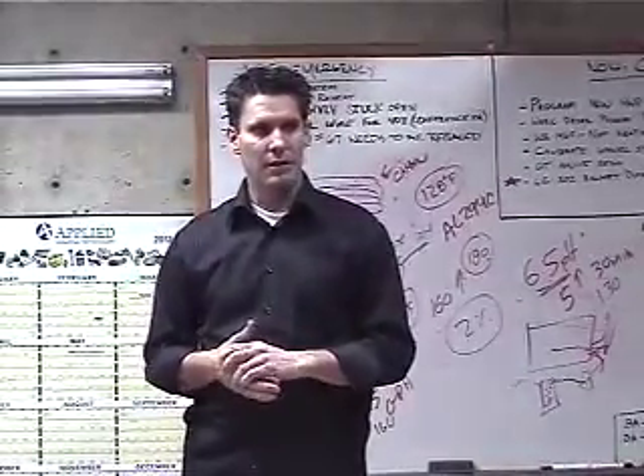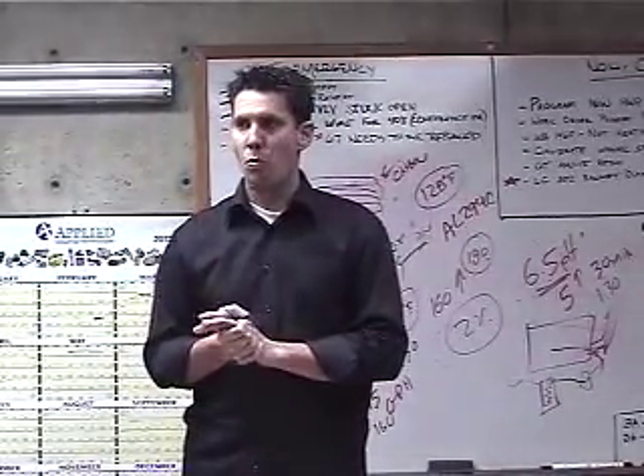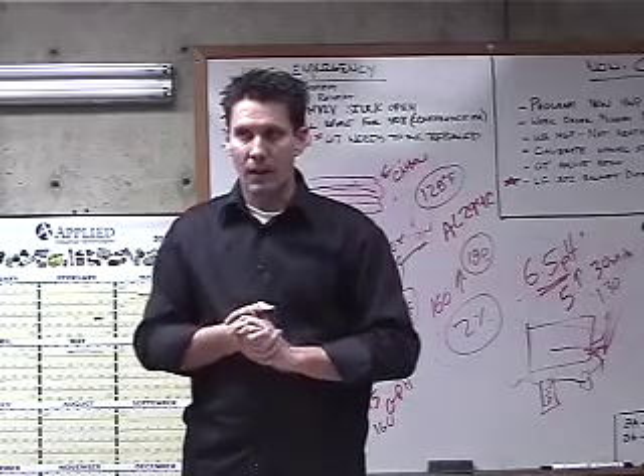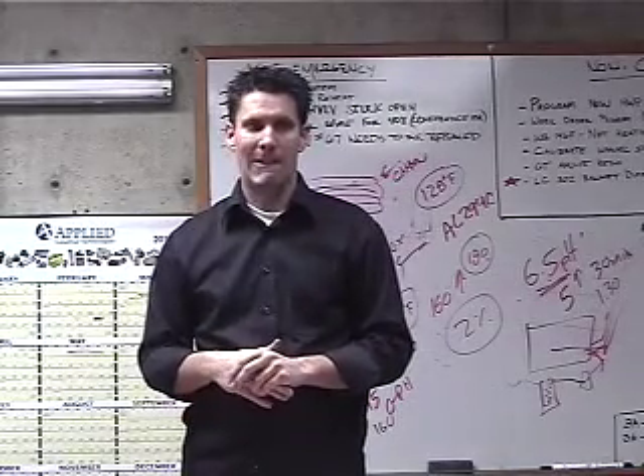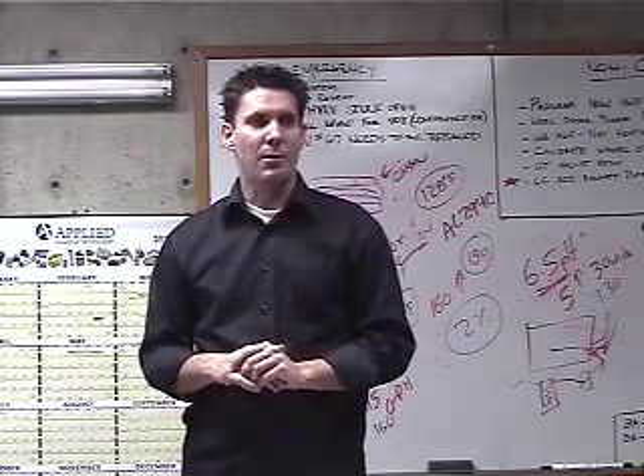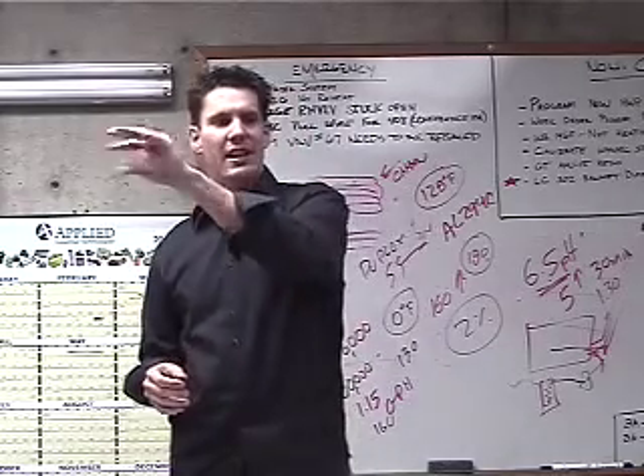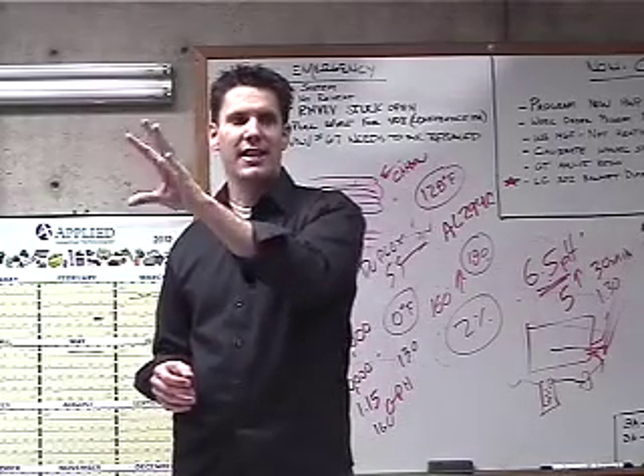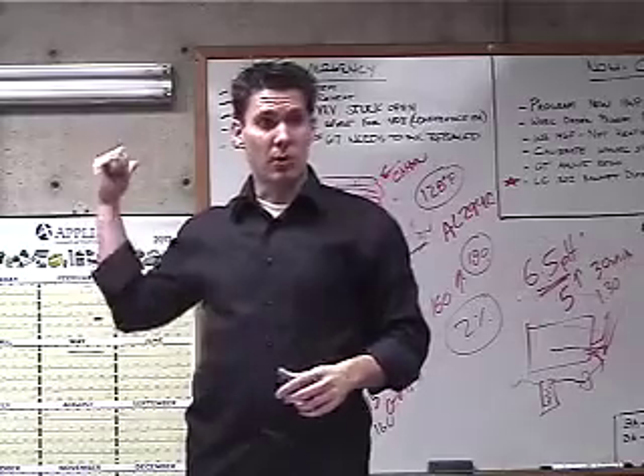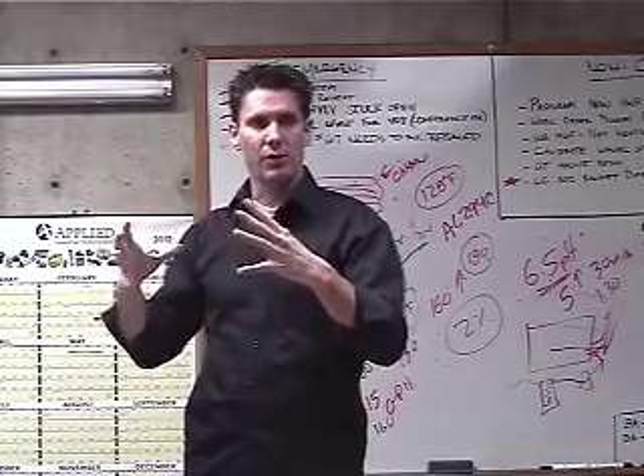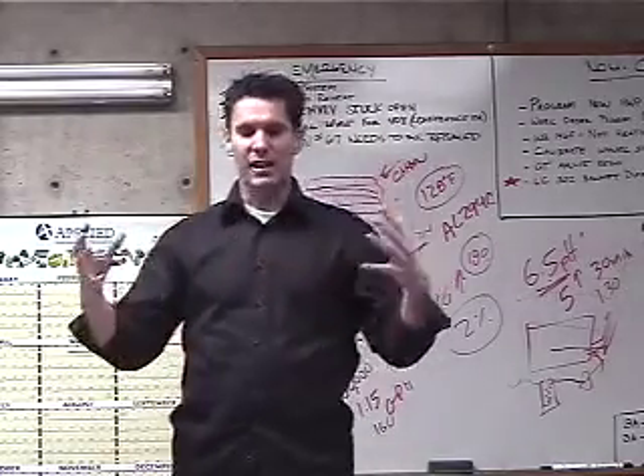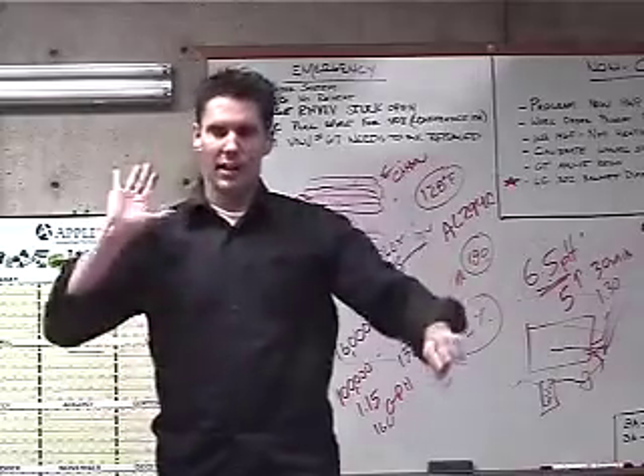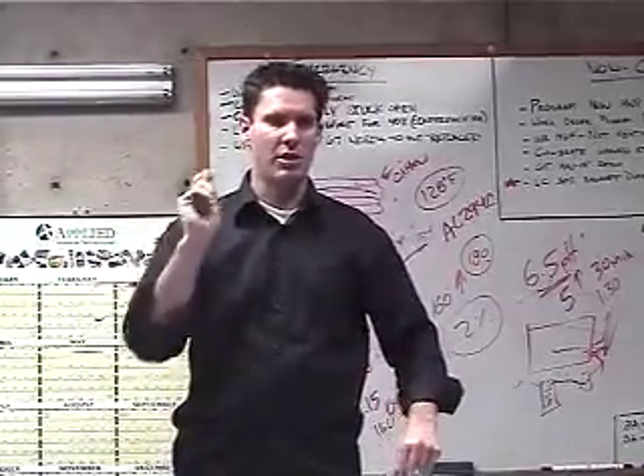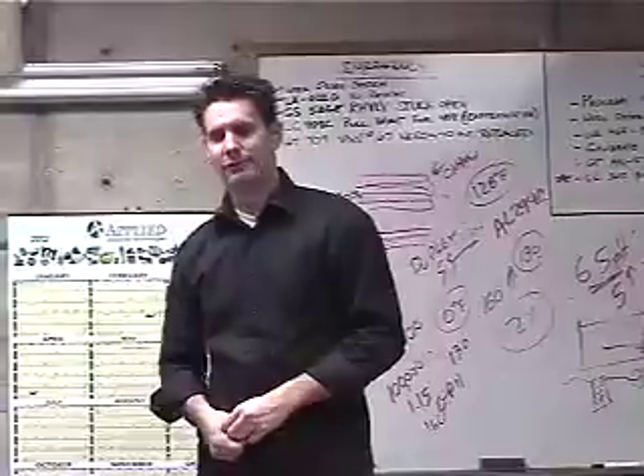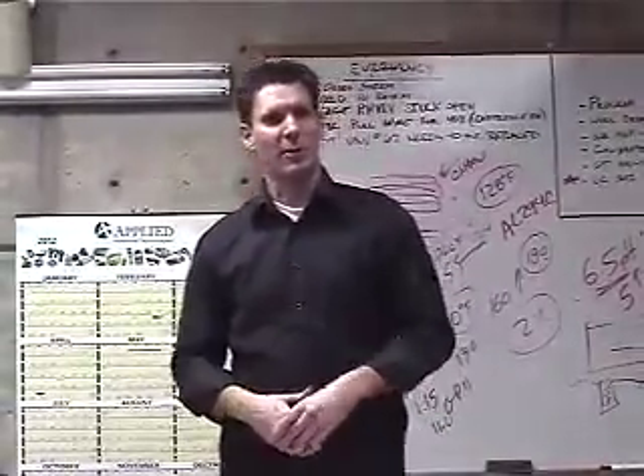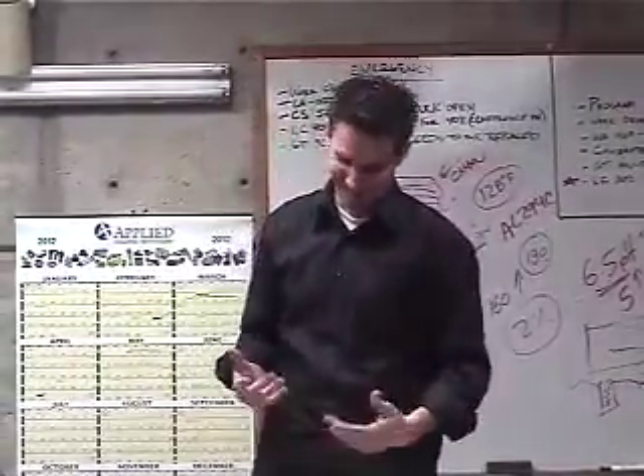Those are tied into our existing switch that we have. Two new switches. There's two new ones, on each door. Yeah, per code, the boilers in that room have to be controlled by switches in that room. And so I'm sure your other boilers have their own E-stop switches on those doors. So as you exit, in case of an emergency, as you exit the door, you hit that switch, just push the switch in and you run. So depending on how scary it is, you might want to run a little faster. Okay.